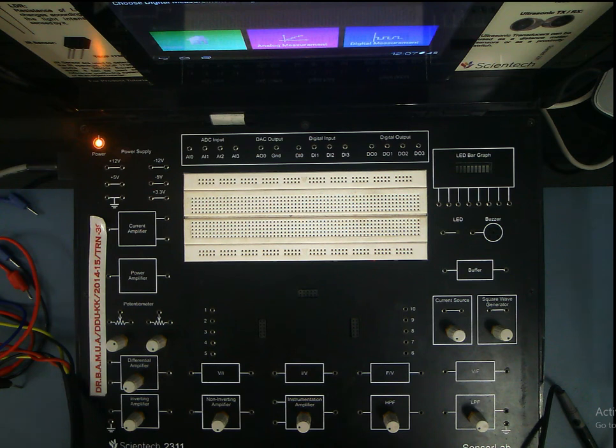It may so happen that output of your sensor is voltage, but you want the output to be in current. It may so happen that output of your sensor is frequency, but normal multimeters are unable to read frequency, and you want that output to be directly fed to some data acquisition system which accepts only voltage. So you have to change your signal from frequency to voltage.